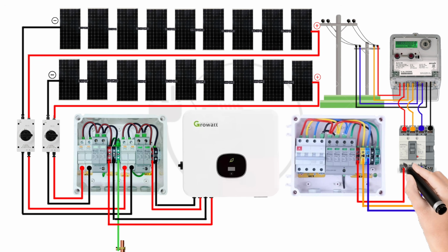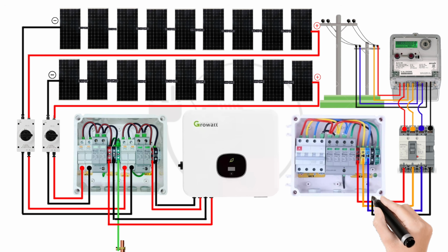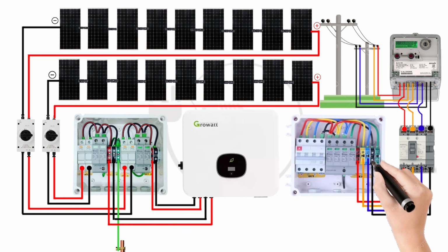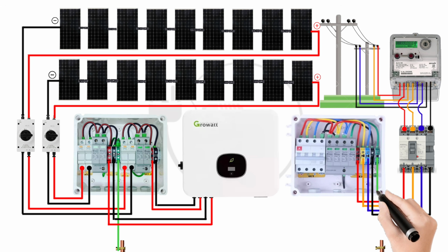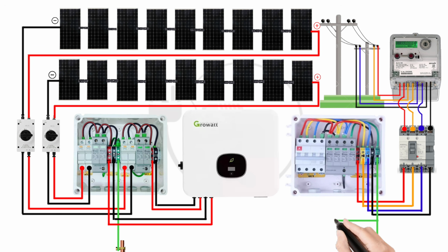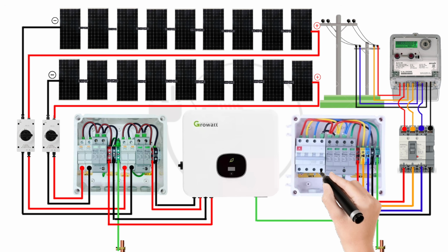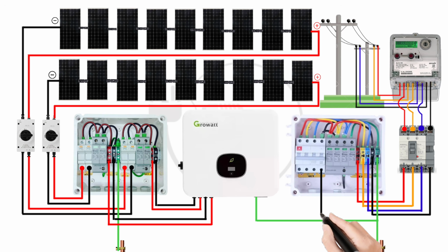Then the SPD is connected in parallel to the input of the 3-phase MCB, or miniature circuit breaker. The SPD protects the system from voltage surges caused by lightning strikes or other electrical disturbances. The ground wire should be connected to the designated ground terminal on the SPD. The MCB provides overcurrent protection, preventing damage from short circuit or overload.